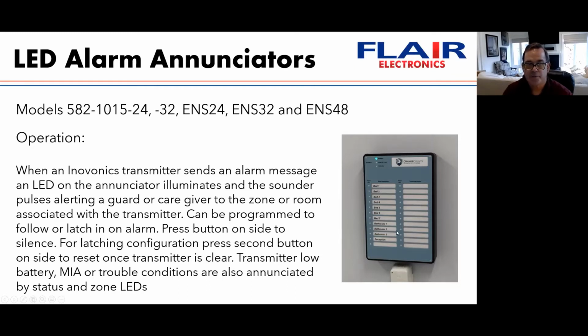The enunciators can be programmed in either a follow or latching configuration. In a following configuration, the LED comes on when a device or transmitter triggers an alarm, and as soon as that transmitter clears, the LED on the panel clears also. In a latching configuration, when an Inovonics transmitter sends an alarm, the LED latches in. The transmitter may clear, but the LED will still remain latched.